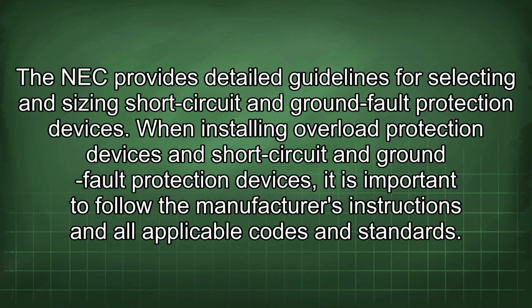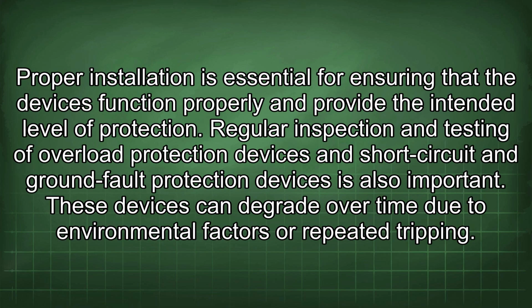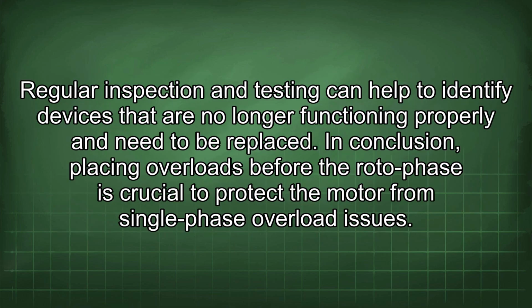When installing overload protection devices and short circuit and ground fault protection devices, it is important to follow the manufacturer's instructions and all applicable codes and standards. Proper installation is essential for ensuring that the devices function properly and provide the intended level of protection. Regular inspection and testing of these devices is also important. These devices can degrade over time due to environmental factors or repeated tripping. Regular inspection and testing can help to identify devices that are no longer functioning properly and need to be replaced. In conclusion, placing overloads before the rotor phase is crucial to protect the motor from single-phase overload issues.